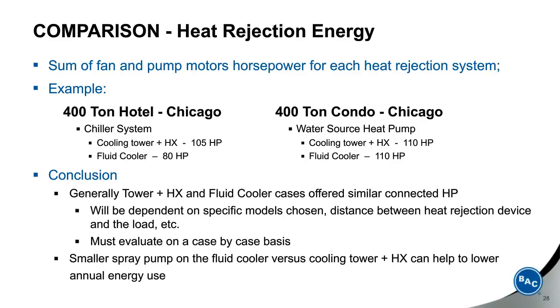Okay. Would there be absolutely no scaling in a fluid cooler? No, there would be scaling. As you evaporate water on the surface of the tube, you will leave some of the deposits there, but that can then be controlled by the water treatment program. If your water treatment program is not being done properly, you can actually build up a layer of scale, which then retards your heat transfer and causes you to use more fan horsepower to reject the heat. However, this scaling can then be cleaned off the outside of the tubes because they're easily accessible once you remove the drift eliminators on top of the unit. You can see the coil, you can inspect it, and know that you have a problem right away. You can adjust your water treatment program, or even get in there and clean it with a high-pressure sprayer, if that will help.